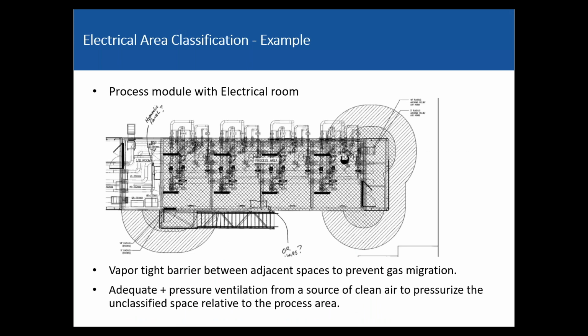Now this is a real life example. We have a process module here with something going on, and we call this a Div 1 area. We have a couple doors, and I'm guessing there's a door here, and there's a vent over here. So the boundary then extends. API 500 and 505 give guidance on, if you have a hazard in this module, how far does this bubble, this hazardous area, go? And this is not an HVAC job to determine. This is where your process safety guy comes in. So the process guy says, it's going to look like this. The process safety guy says, here are your Div 1, Div 2 boundaries. HVAC guys get involved for guidance, usually between the process safety and electrical guys.